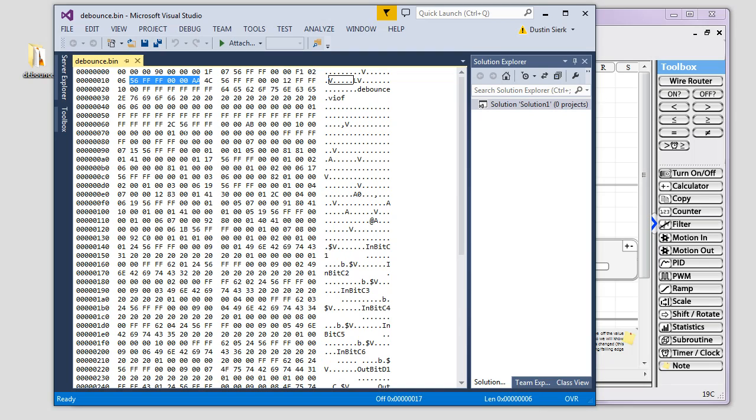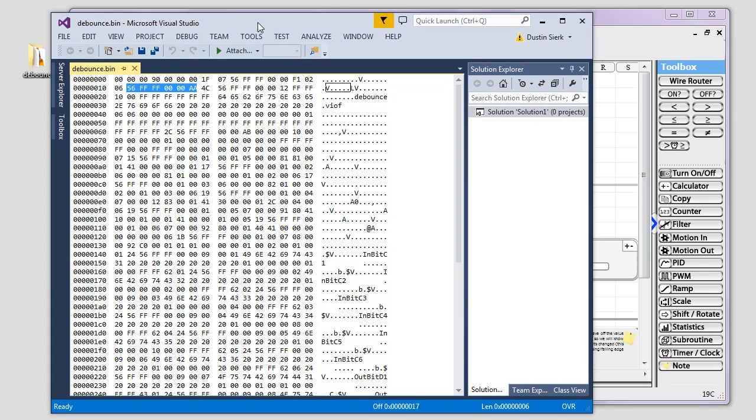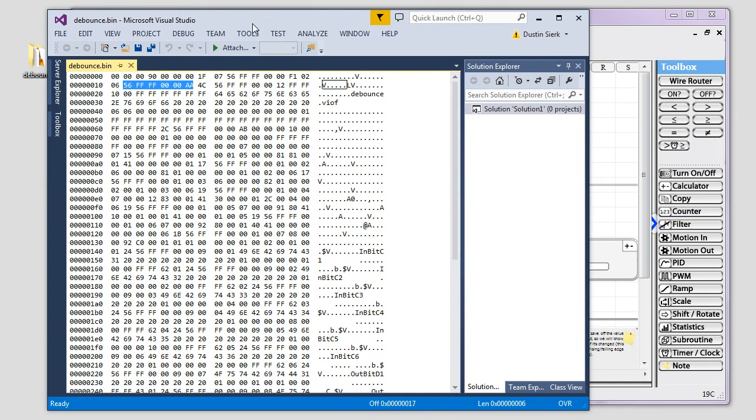This happens to be a very small one. Most applications will be a good bit longer than this. When you're doing this, you send one message at a time to the PLC, and then you wait for a response. And you may want to go ahead and have a timeout there in case the PLC, for whatever reason, is being too slow. You might want to recognize that and try resending. But the responses you're getting back, the important part is the byte number 7. You're going to want to see hexadecimal 6 come back in byte 7. That's an acknowledgement, and as long as you get that, then go ahead to the next message.